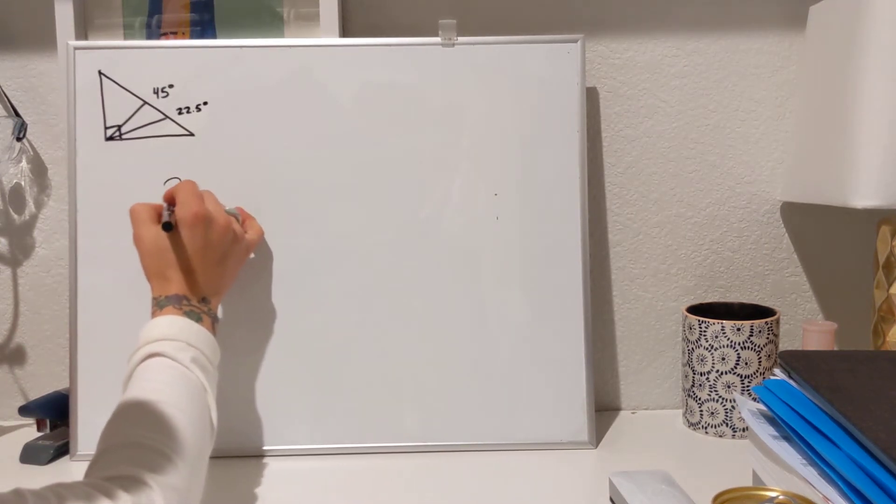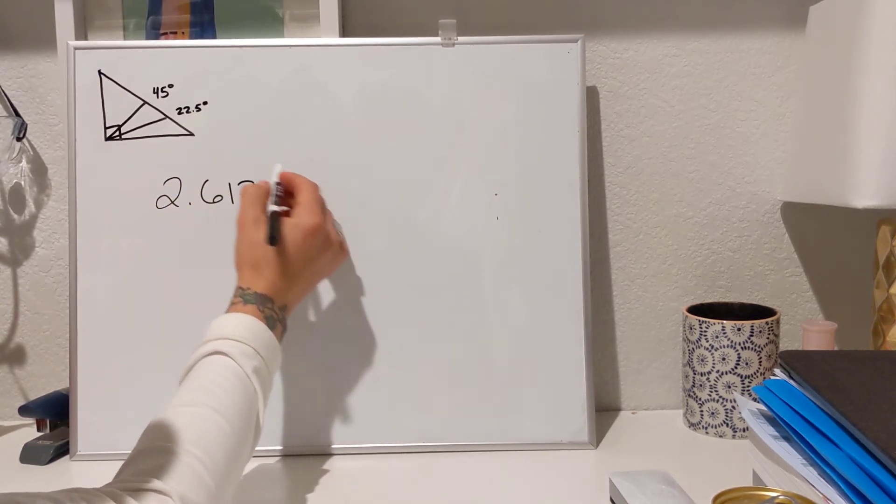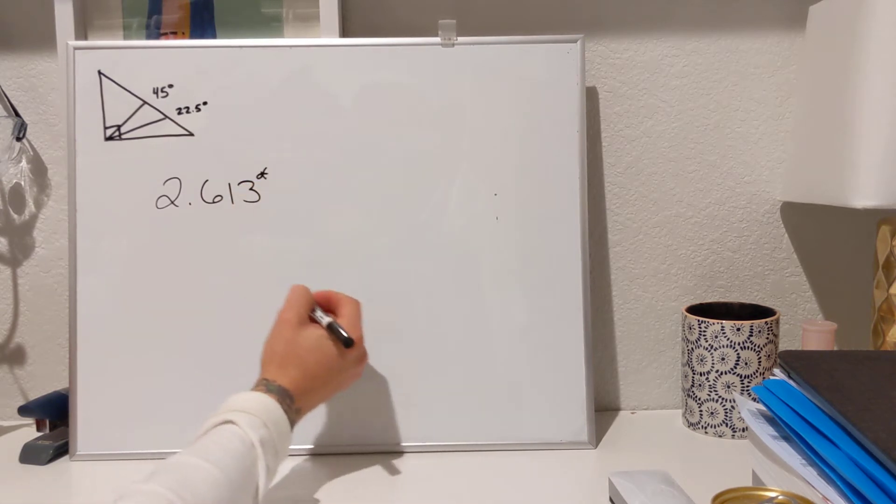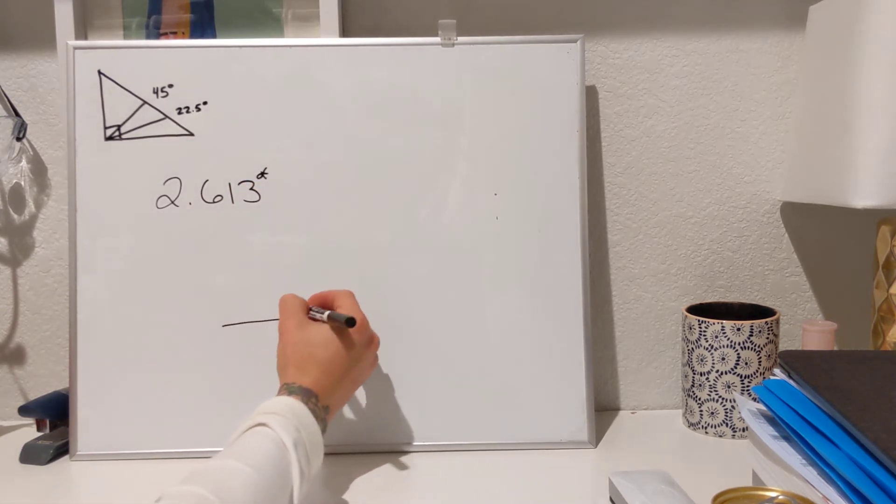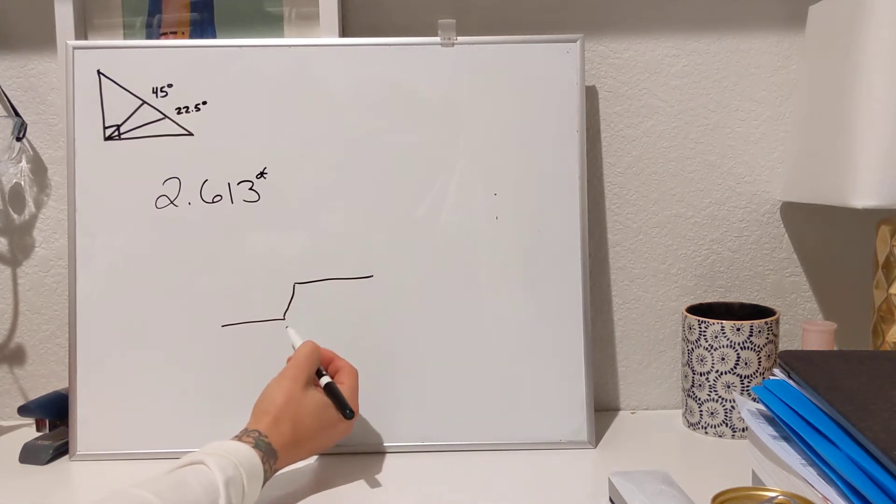So a 22 offset, your formula is going to be 2.613. That is the magic number. So say you have an offset that comes here and it comes here and it comes here. You have to find out that distance.